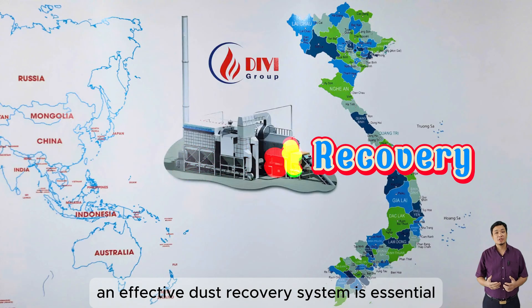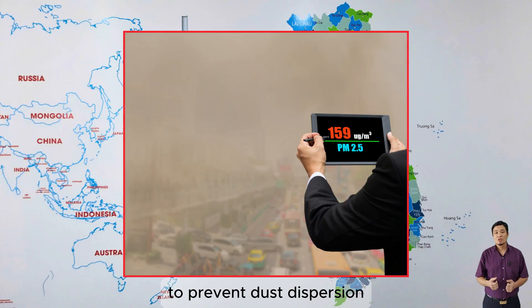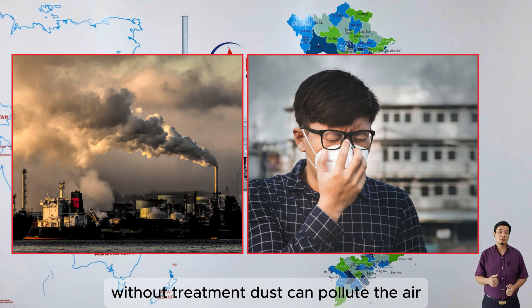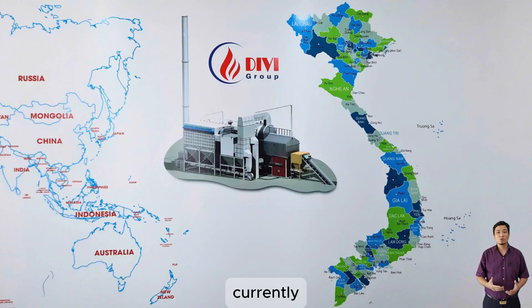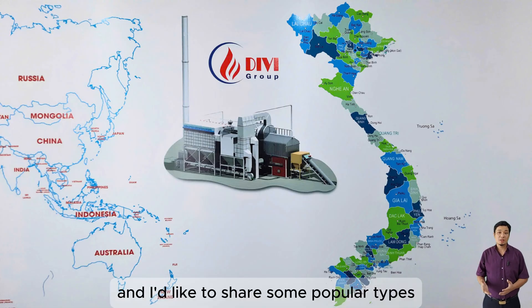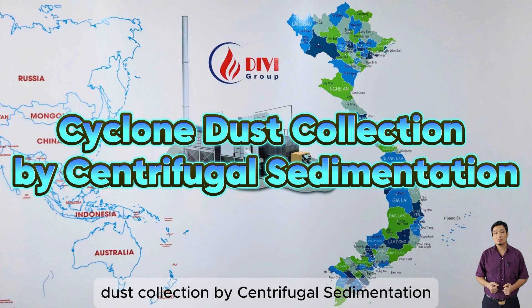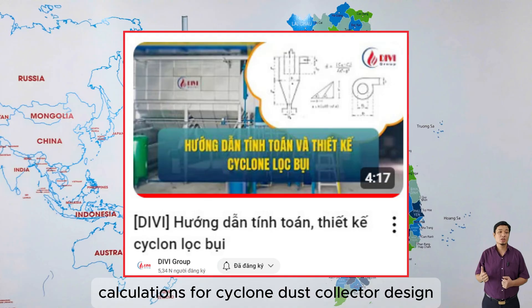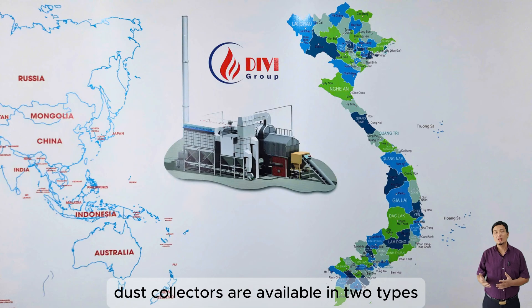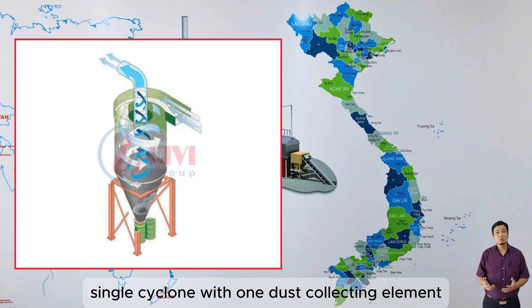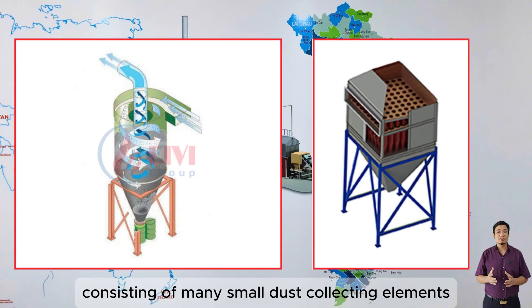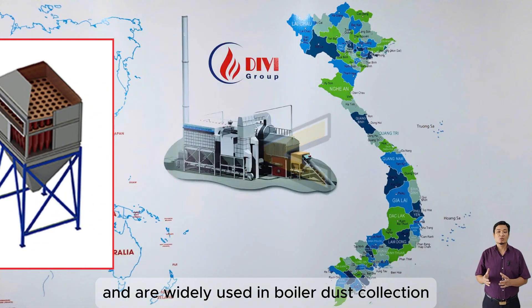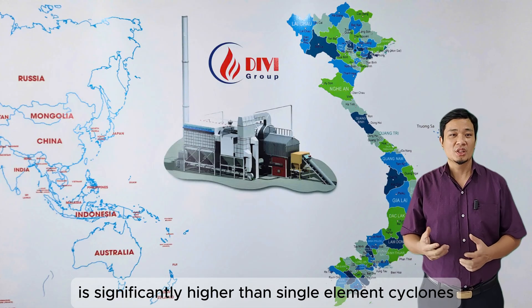Issue 2: Dust Recovery. An effective dust recovery system is essential to prevent dust dispersion into the environment. This system collects all the dust generated during fuel combustion. Without treatment, dust can pollute the air, harming the environment and human health. Currently, there are many types of dust recovery systems. Cyclone dust collection by centrifugal sedimentation is available in two types: single cyclones with one dust collecting element, and multi-cyclones consisting of many small dust collecting elements. Multi-cyclones are much more efficient than single cyclones and are widely used in boiler dust collection, though their manufacturing cost is significantly higher. Cyclones are only effective for recovering dust particles larger than 10 microns.